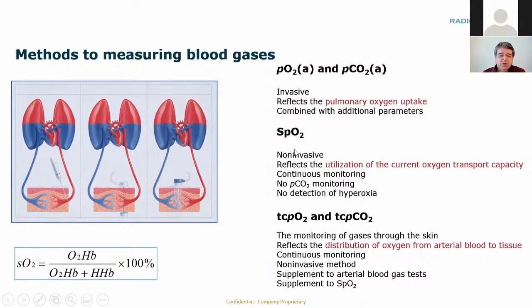SpO2, which you are getting from pulse oximeters, is not exactly the same as SO2 saturation, which you are getting from a blood gas analyzer, but the basic calculation formula is the same. So the big advantage of this method is that it's non-invasive. It reflects utilization of current oxygen transportation capacity. It's continuous, but you don't have carbon dioxide in monitoring. And because of physiology, because of the shape of the oxygen dissociation curve, you cannot detect hyperoxia, which is extremely important to avoid in newborns, by pulse oximetry. It's not a deficiency of methodology or technique as such, it's just physiology, this oxygen dissociation curve, which does not allow you to detect high PO2s at very high levels of saturation.